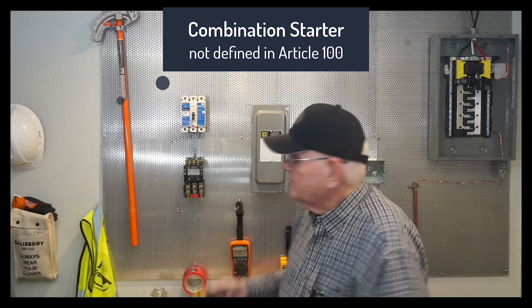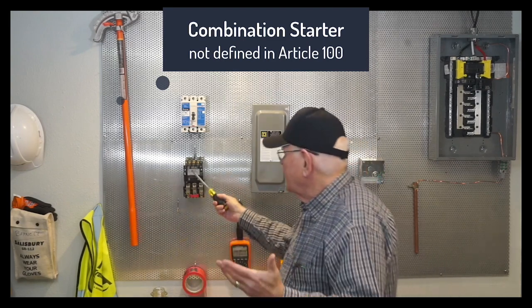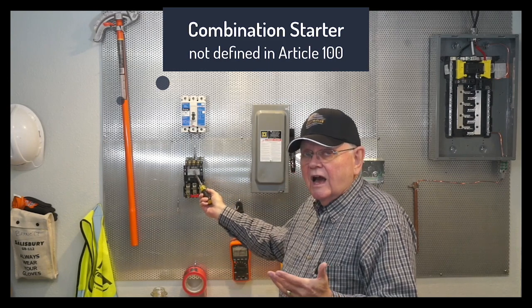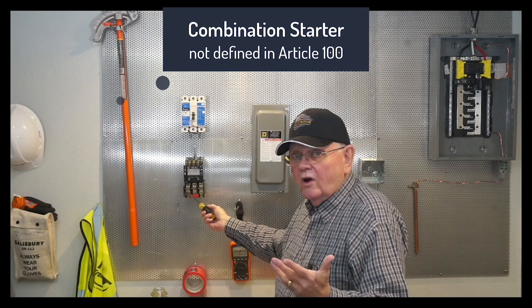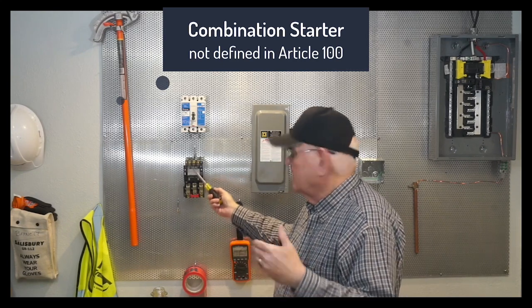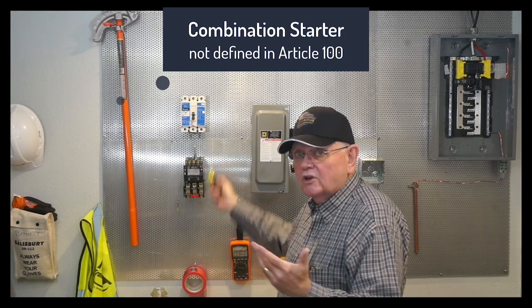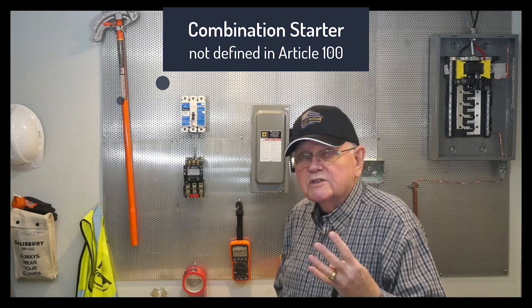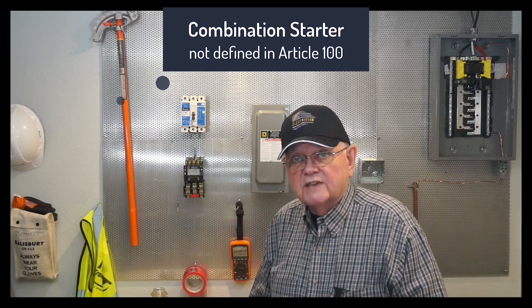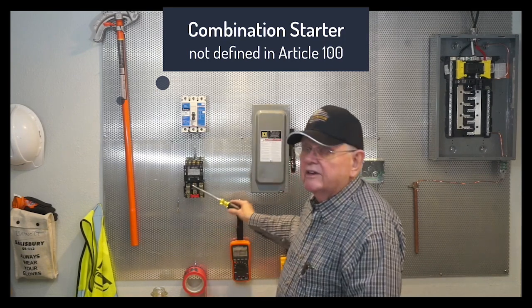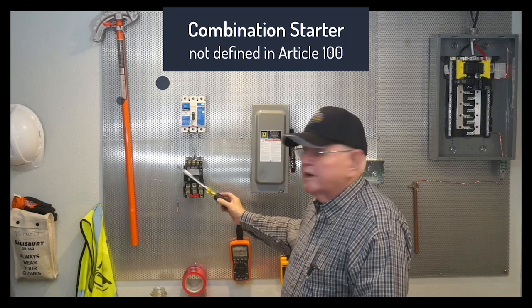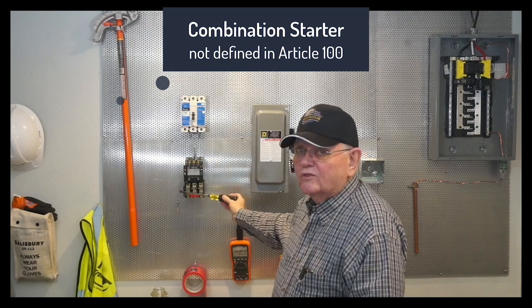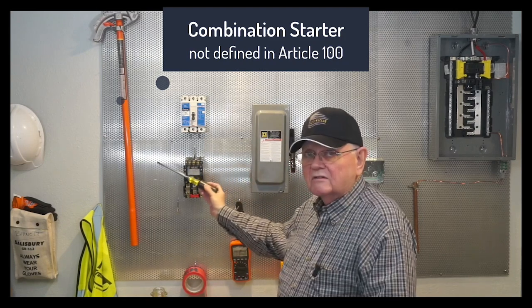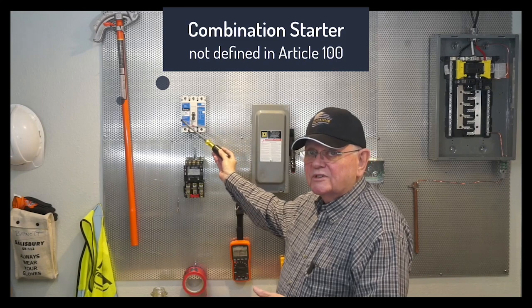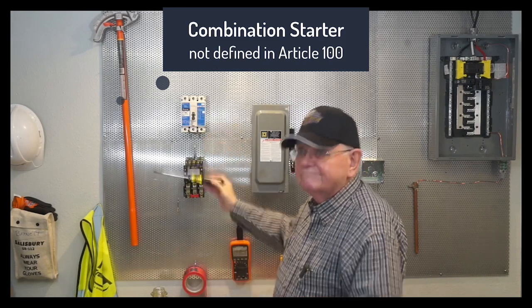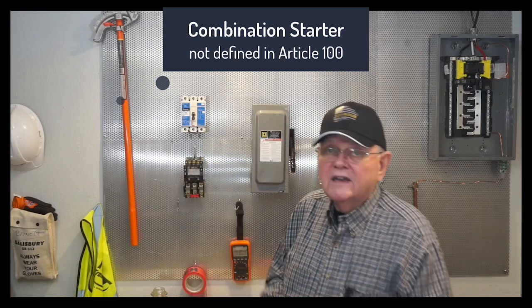And then the next requirement is I have to have some way to start and stop my motor. So inside of my starting contactor, I have some contacts. When I energize the coil that controls the motor starter, it of course closes the contacts, and that allows current to flow to the motor. The fourth requirement to be a combination starter is I have to have overload protection. So I have overload protection down here on the bottom of what we call the starting contactor. When they manufacture the starting contactor and the overload relay together, the whole unit is called a motor starter. And if I provide my short circuit and ground fault protection and disconnect switch all in the same configuration like this, then I have a combination starter.